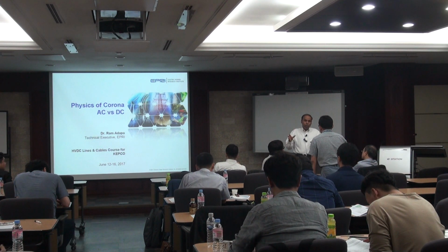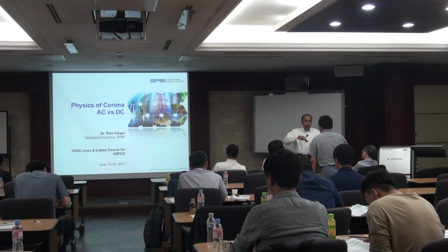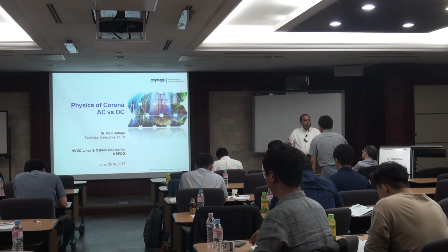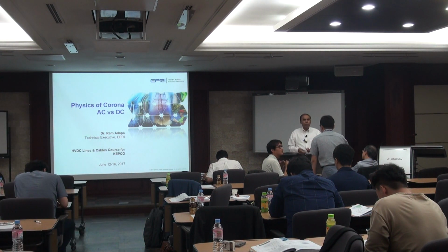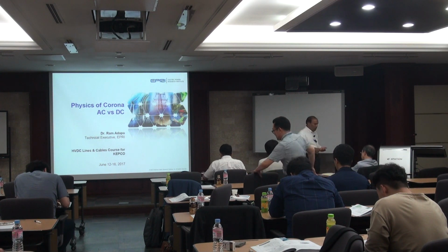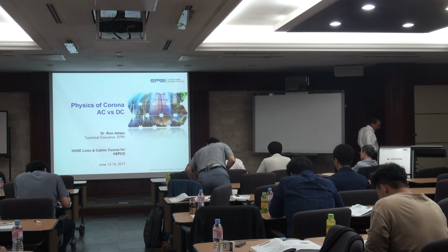But if you have more than 2 converter stations, like a DC mesh, and you don't have DC circuit breakers, you have to bring all 3 or 4 terminals down. The whole DC network goes down. So you don't want that, and that's why you want DC breakers. You're welcome. Okay, let's start again.